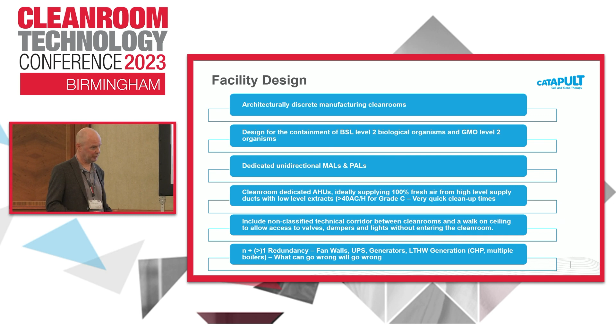If you're operating HVAC with a single fan, single inverter, you've got a single point of failure. If that goes down, you're going to have to draw a line under what you're doing, clean down and start from scratch. So in the past, we found the use of fan walls as opposed to single fans gives you a level of redundancy because the HVAC can operate and the necessary absolute and differential pressures can be maintained even if you have a partial failure of your fan wall. Same goes for UPS backup, generators, low temperature hot water generation. Because inevitably, if you've worked in this industry a while, you will know that what can go wrong will go wrong eventually, despite all your best efforts. So where you can build in redundancy, it's definitely worth doing.